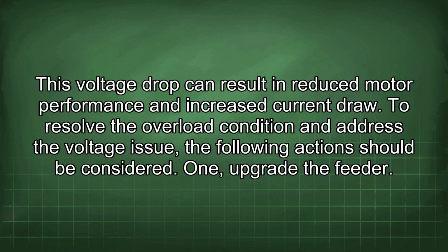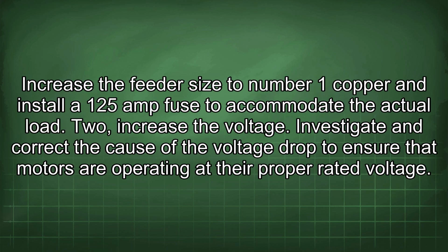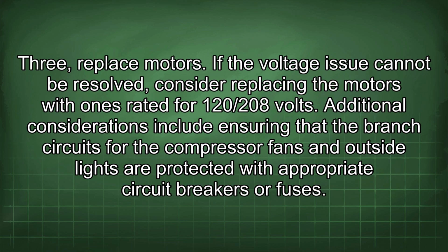1. Upgrade the feeder. Increase the feeder size to number 1 copper and install a 125 amp fuse to accommodate the actual load. 2. Increase the voltage. Investigate and correct the cause of the voltage drop to ensure that motors are operating at their proper rated voltage. 3. Replace motors. If the voltage issue cannot be resolved, consider replacing the motors with ones rated for 120/208 volts. Additional considerations include ensuring that the branch circuits for the compressor fans and outside lights are protected with appropriate circuit breakers or fuses.